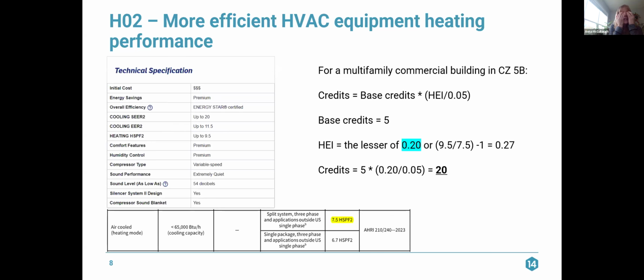This is an example of a split heat pump. So you'll see the technical specification for this example piece of equipment on the left there, and then at the bottom we have the requirement for that piece of equipment from section C403. So we assumed a commercial multifamily building in climate zone 5B. All units are being served by these heat pumps. The base credits for a multifamily building in climate zone 5B for H02 is 5. And you'll see here that we're just assuming this 9.5 HSPF2 for the sake of this very short presentation.